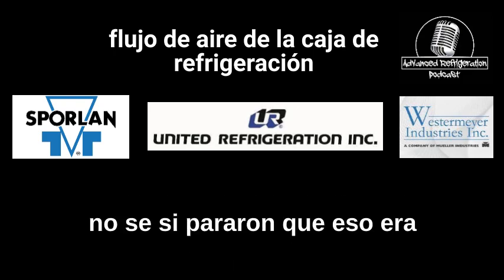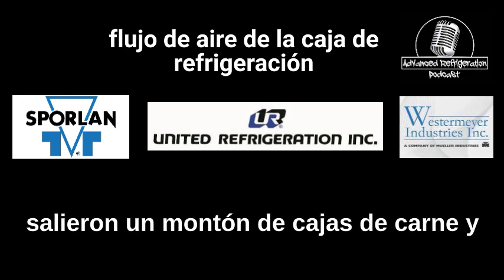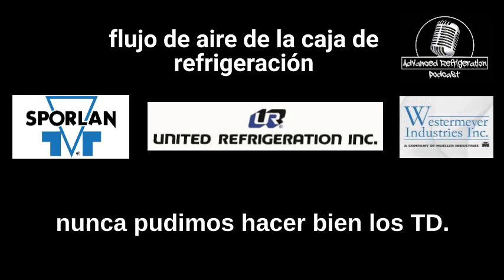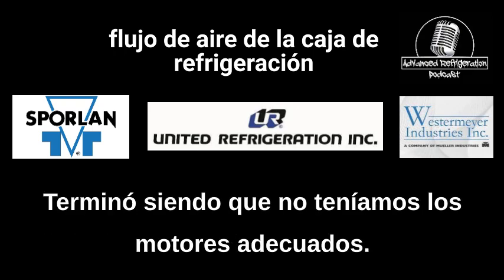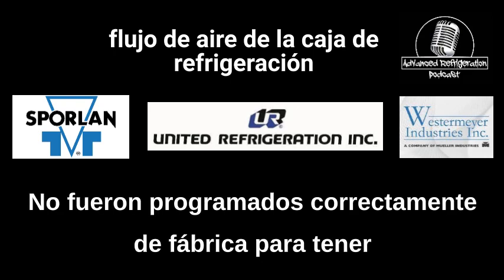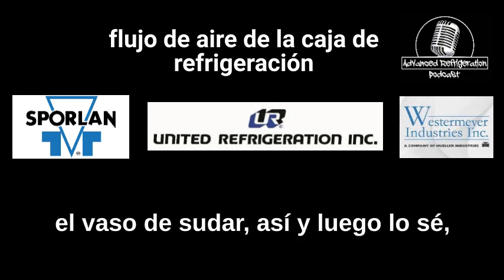I don't know if they stopped that. That was going around when they were doing these, because we had a bunch of meat cases come out, and we never could get the TDs right, no matter what we did. It ended up being that we didn't have the right motors. They weren't programmed correctly from the factory to have that increased airflow on those meat cases to keep the glass from sweating.